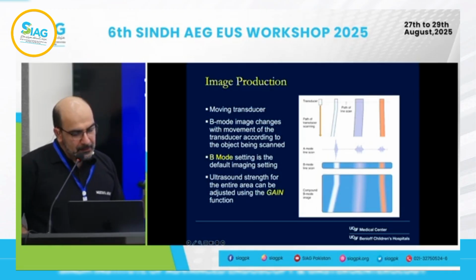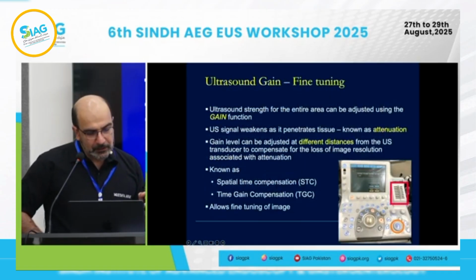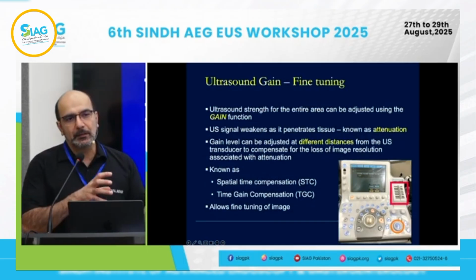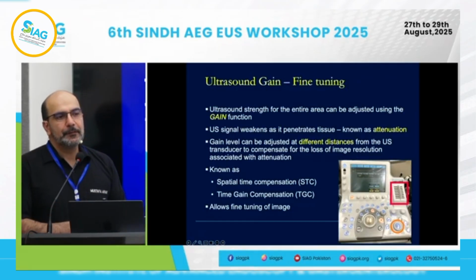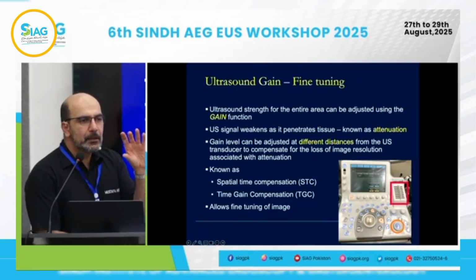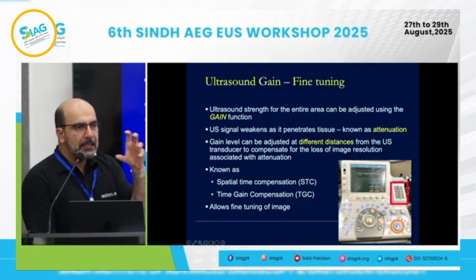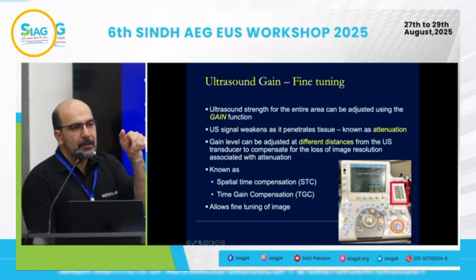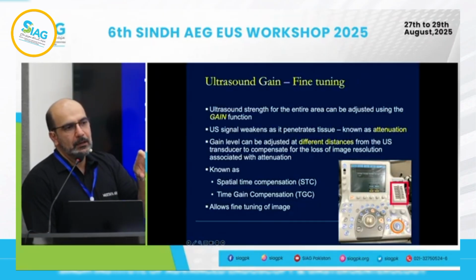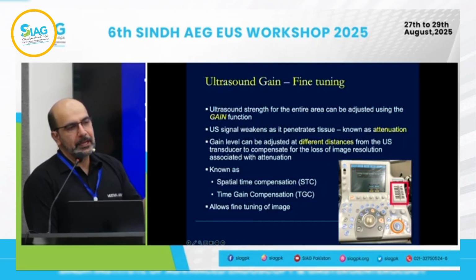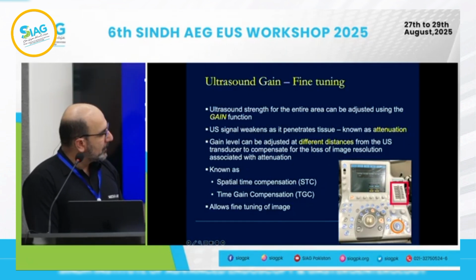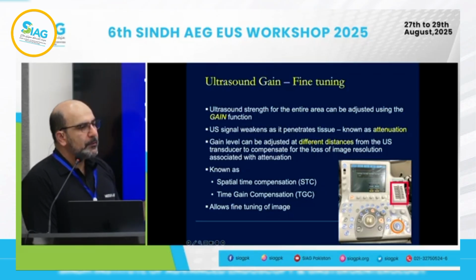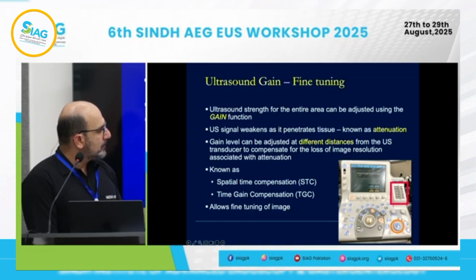The other important thing is the gain function, which I'll show you here too, but gain is essentially the strength of your ultrasound signal. So if your image is not very clean and you're not seeing it very well, you may have to increase the strength of your ultrasound signal. That's your gain. The easiest way to find gain on the bigger consoles is the largest dial on the right lower corner. We have two different setups. I think we have the big console today that you'll see, the Aloka, and then you have the ME2 from Olympus.